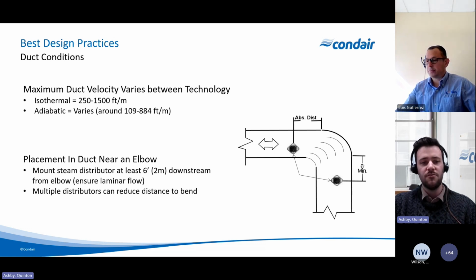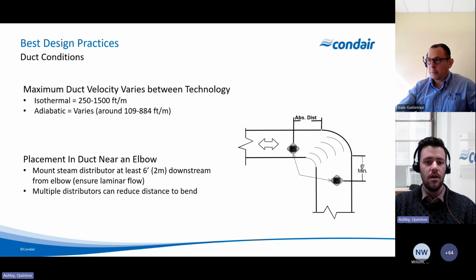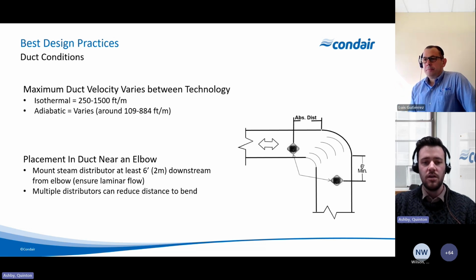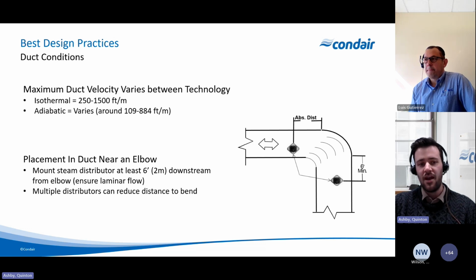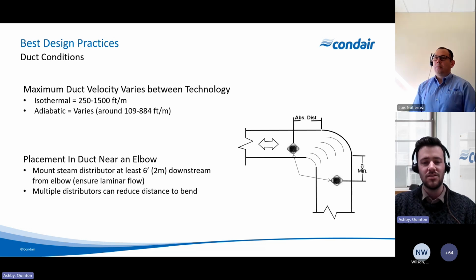On the other side, in terms of placement, we want to make sure that we're placing humidifiers correctly in terms of any obstructions or elbows. So if we are upstream from an elbow, we want to make sure we're at least giving the absorption distance, maybe a little bit of a safety factor as well. And if we're downstream from an elbow, we want to make sure we're at least around 6 feet. So this is very safe, but we want to make sure that there's laminar flow, and typically that's as far from the bend as possible.